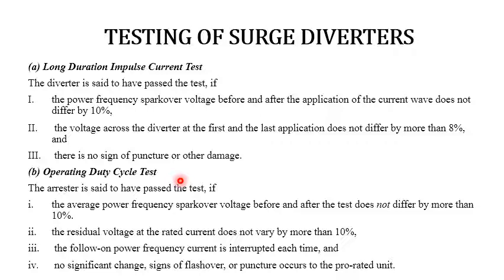In the course of the application of the current wave, if the power frequency voltage is reduced during the flow of the current, it can be compensated up to a maximum value of 10% of the overvoltage. The time interval between each application is about 1 minute, and between successive groups it is about half an hour.